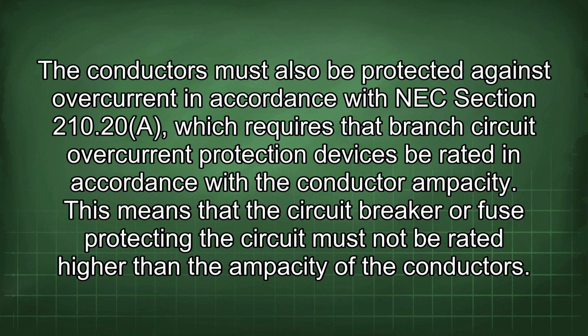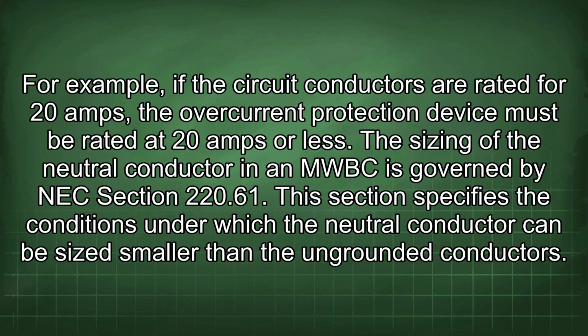210.20(A), which requires that branch circuit overcurrent protection devices be rated in accordance with the conductor ampacity. This means that the circuit breaker or fuse protecting the circuit must not be rated higher than the ampacity of the conductors. For example, if the circuit conductors are rated for 20 amps, the overcurrent protection device must be rated at 20 amps or less.